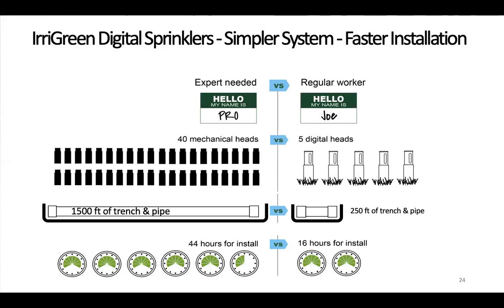So for a typical residential install that takes 44 hours, we're bringing that down to 16 hours. For commercial systems this has a bigger benefit, because in many places commercial systems are installed with union labor, so labor rates for installation can go up significantly. Overall you can save a lot of money on the project if you reduce that labor by using something like digital sprinkler heads.